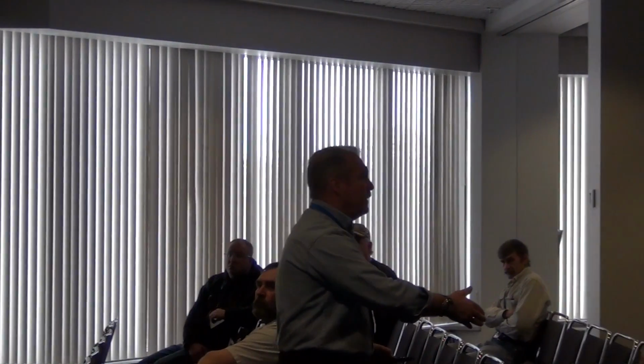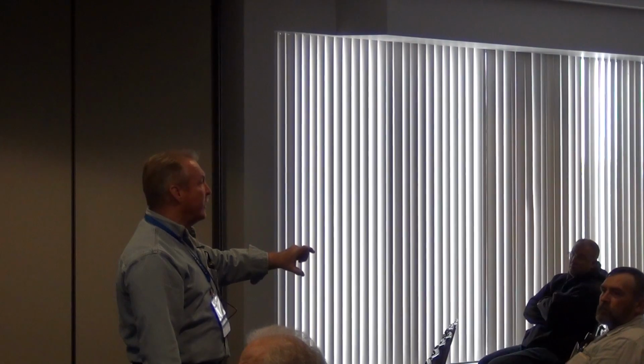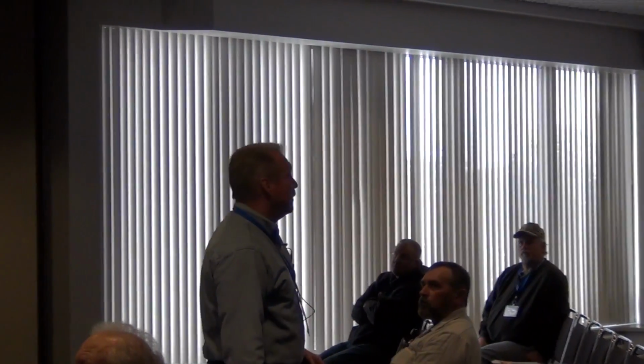Centrifugal ventilators, this is centrifugal, comes in here, goes out at a right angle, more powerful, a little bit heavier, but a more effective ventilator as far as airflow movement. Remember bends reduce flow? Bends reduce flow. You see some of the pictures, you've got a ton of bends. For every bend, you're reducing that ventilator about 20 to 60%. So your flow, all ventilators are rated. If you see a little number on the side, it'll say free air. Like this axial ventilator is actually at 1285 cubic feet per minute with no bends. At one bend, as it's going over the edge here, it drops 40%. With two bends, it drops 60%. So bends reduce flow. You need to recognize that.